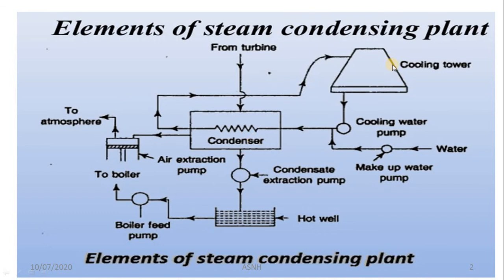So the main function of the cooling tower is to collect the heat from the condenser by circulating the cooling water in the passage of the condenser shell, and then heat transfer takes place and latent heat is responsible for changing the phase of the working substance from steam or vapor to liquid. And whatever condensate is available at the end of the condensation process is collected in the hot well through the condensate extraction pump.